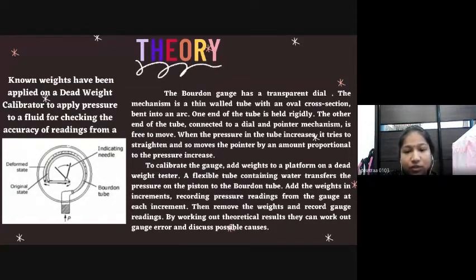Many engineering applications use the Bourdon gauge. The figure shows the simple structure of a Bourdon gauge. The apparatus is a Bourdon gauge connected to a dead weight tester. The Bourdon gauge has a transparent dial that allows us to see the working mechanism. The mechanism is a thin wall tube with an oval cross section bent into an arc. One end of the tube is held rigidly. This end admits pressure. The other end of the tube, connected to a dial and pointer mechanism, is free to move. When the pressure in the tube increases, it tries to straighten and so moves the pointer by an amount proportional to the pressure increase.